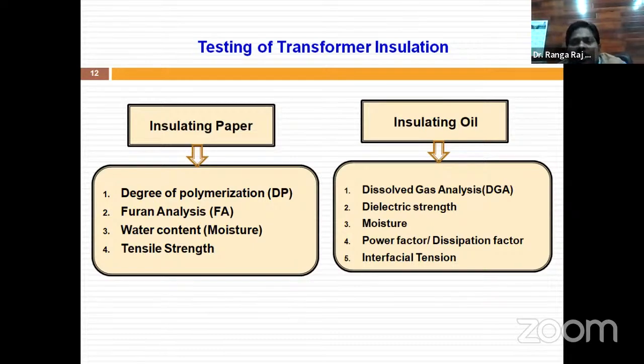Next is dielectric strength. We all know this, we performed this test in our basic courses also, in BTech. It gives the dielectric breakdown voltage of the oil, that is, the maximum voltage that can be applied to the oil, the maximum electrical stress it can handle. Then there's moisture content - we observe the water content in oil, mostly as compared to paper. First water enters as moisture, then it enters the paper.